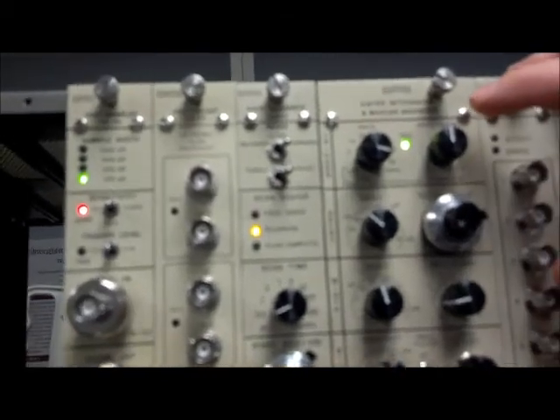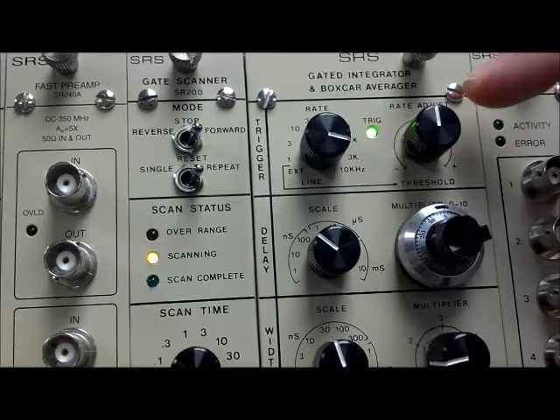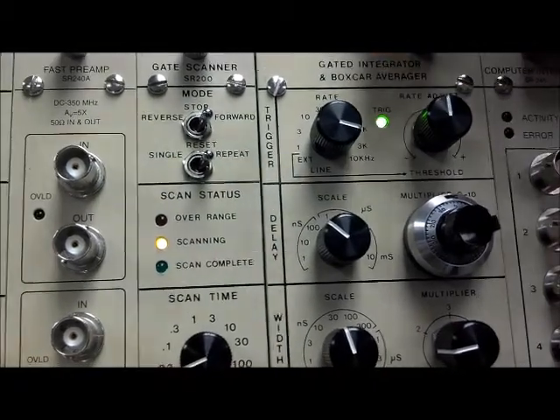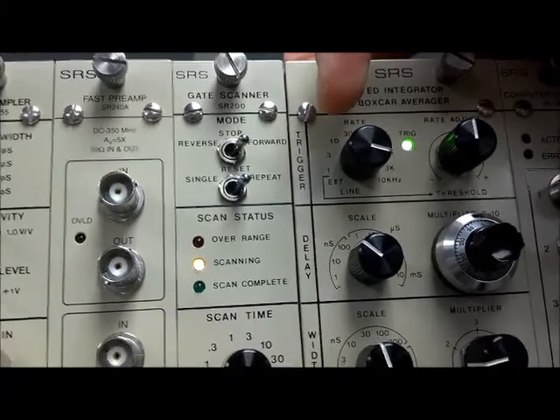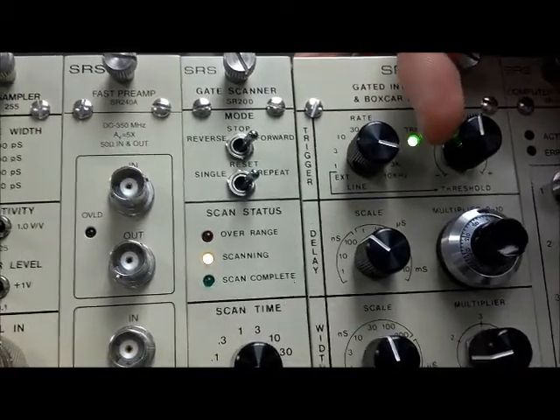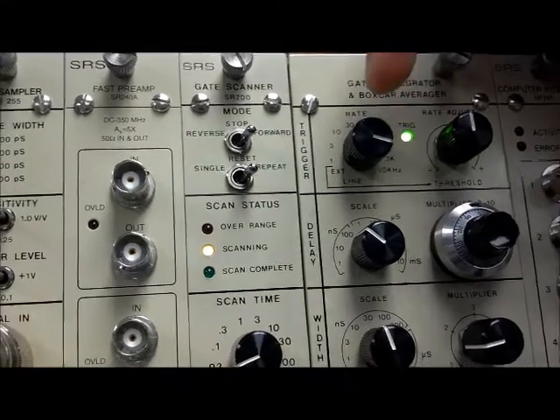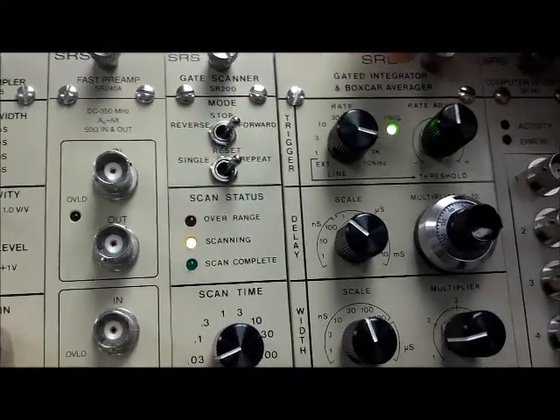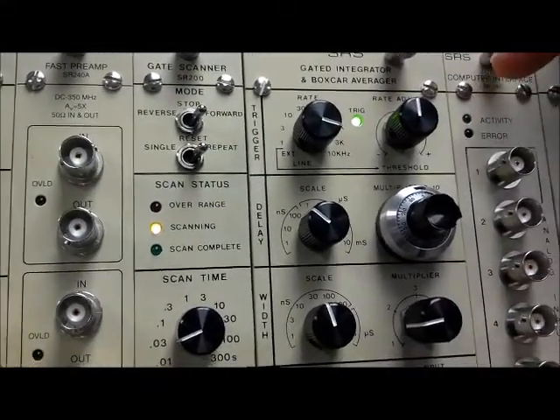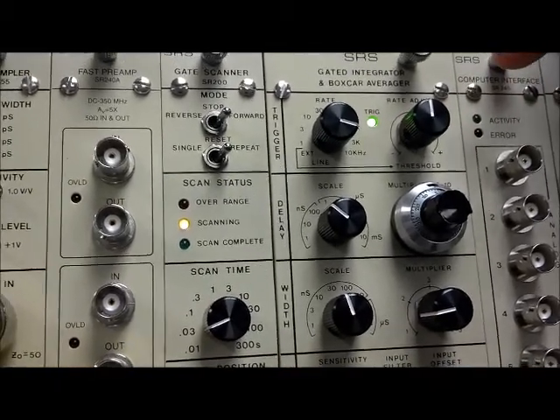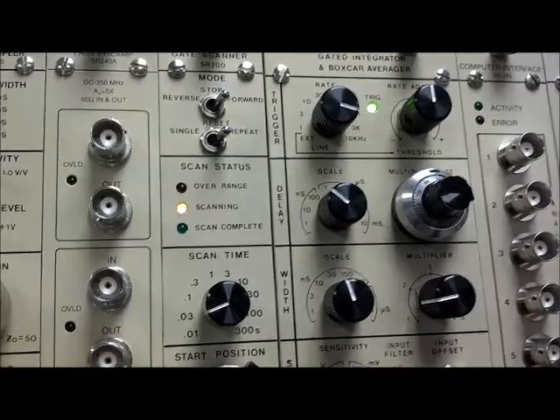The first section is the trigger section. All the trigger is, is a waveform that is generated that allows the boxcar to generate the gate signal. It is adjustable through 1Hz up to 10kHz. You can also use an external trigger. This is continually adjustable through the rate adjust knob, allowing the user to select any multiple of the frequencies between 1 and 10kHz.